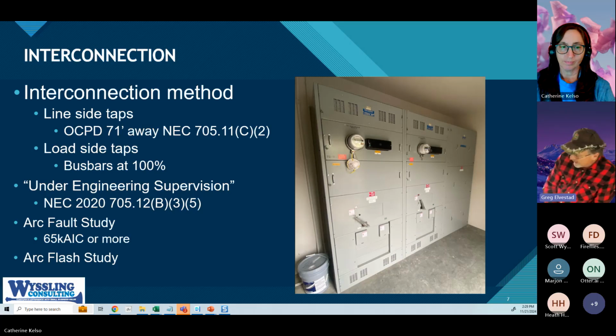Well, for example, you have an 800 amp bus bar. Your PV design puts you in a position where you can interconnect 150 amps of capacity. Well, under your traditional 120% rule, you can't do that. Let's get the numbers right. Take a 400 amp load center, 80 amps limitation there. With 800, you could go 160 amps. So you'd say 200 amps of PV interconnection. Pardon the incorrection there. You've got 200 amps of capacity, but your bus can only take 160. What do you do? Do you derate?